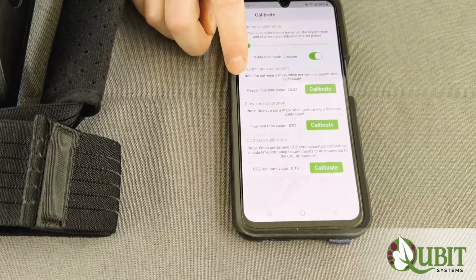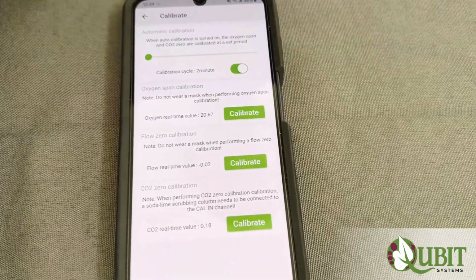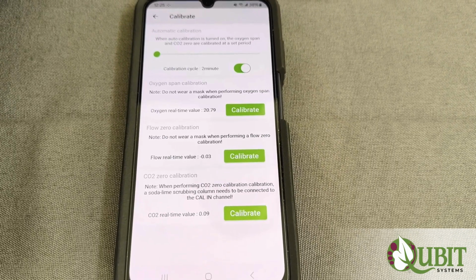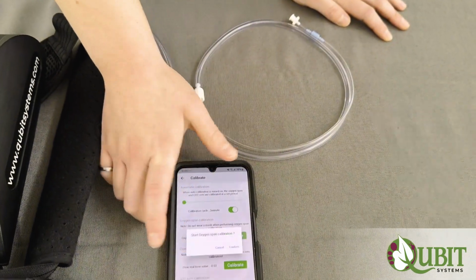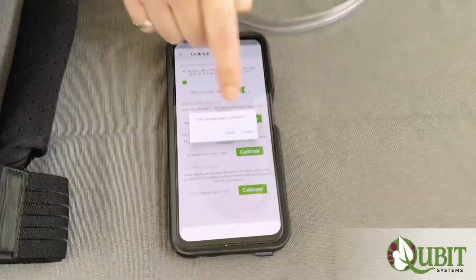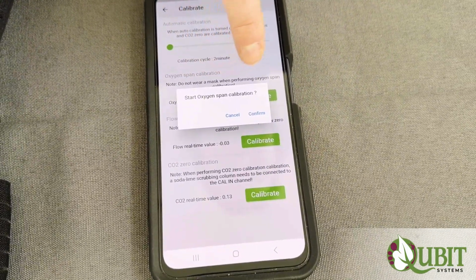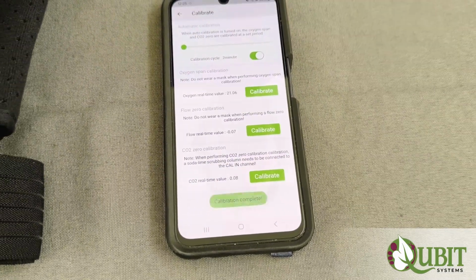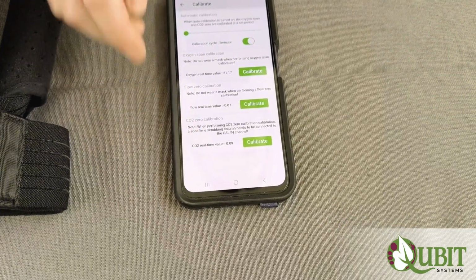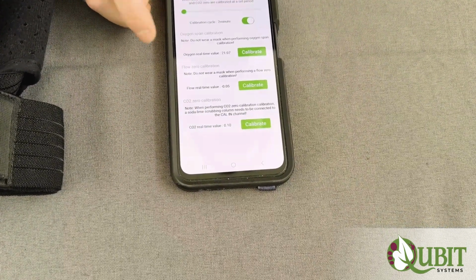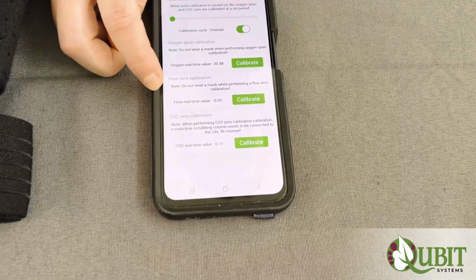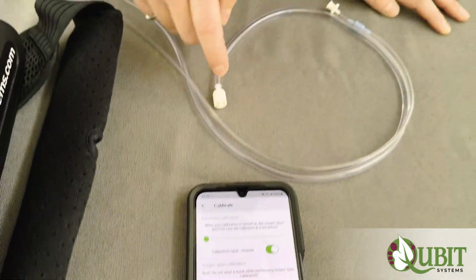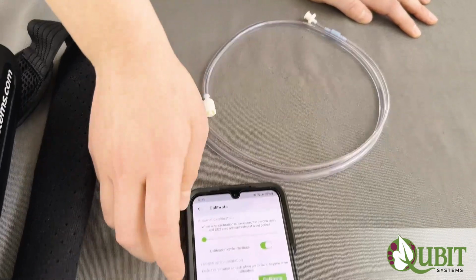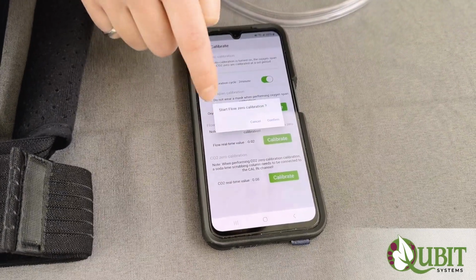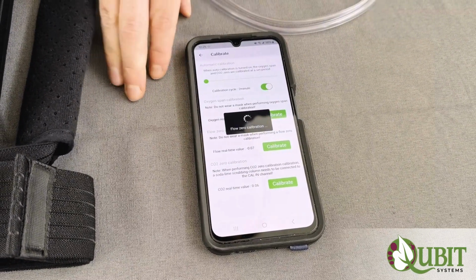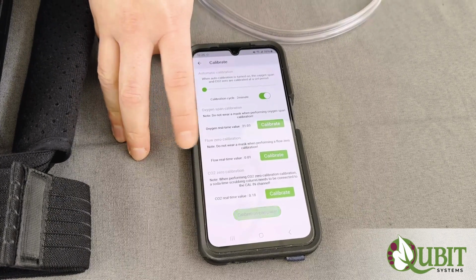Next is the oxygen span calibration, making sure that the gas tube is just pulling from ambient air. Hit calibrate, and then this window will come up saying start oxygen span calibration. Hit confirm, and then wait for this calibration complete message to appear. Next is the flow zero calibration. Ensure that nothing is connected to this tube and that it is not blocked. And then hit the calibrate button, again, confirm, and now the flow signal has been zeroed.